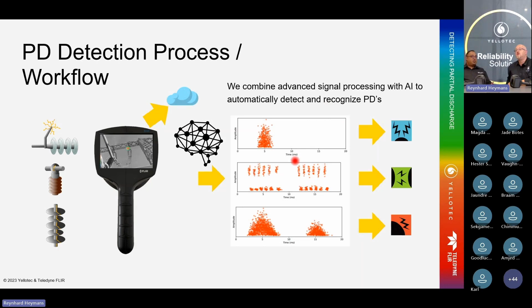Based on the actual frequency of the sounds or the breakdown, it uses AI to distinguish exactly what type of PD it is and how destructive or not it may be. And it's as simple as three inputs, very similar to how you were doing your LEDs. It's exactly the same. You've got your distance. Distance is always very important. Then you've got your voltage, okay? And thirdly, location. Location meaning component. Is it a corona ring? Is it a transformer? Is it a termination?